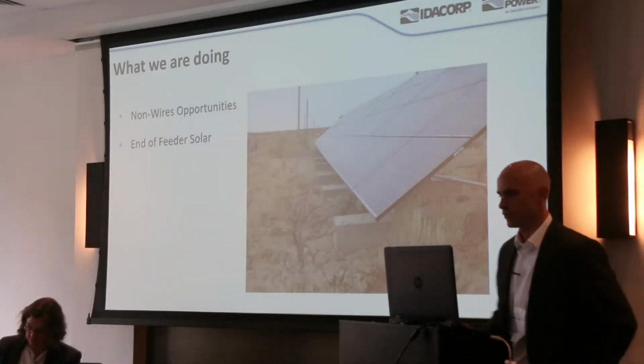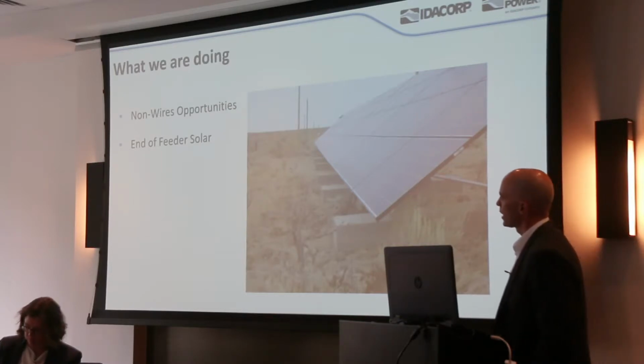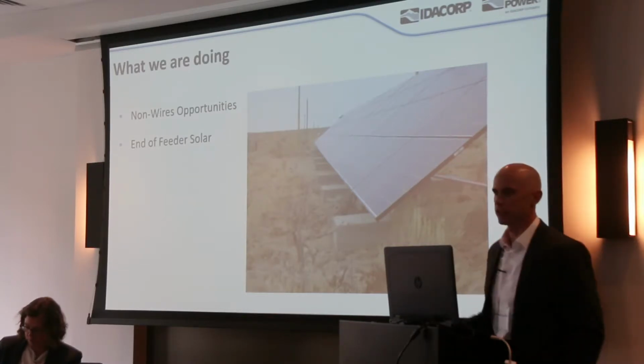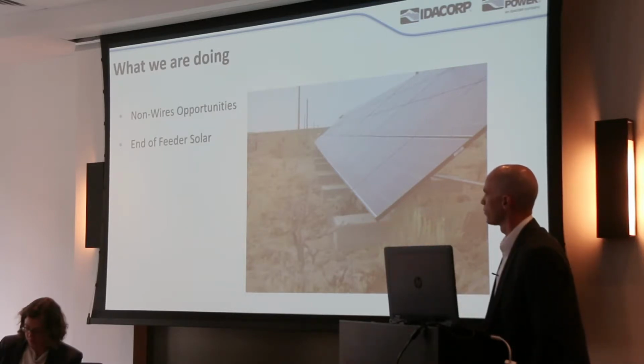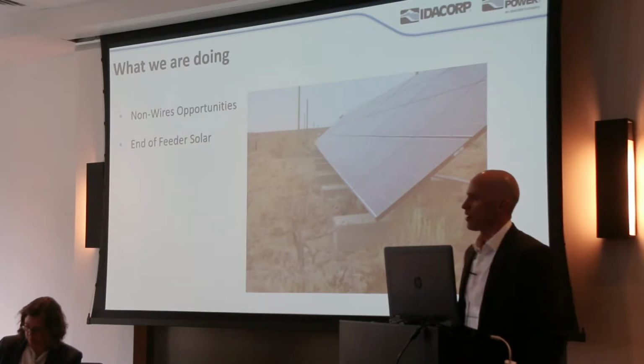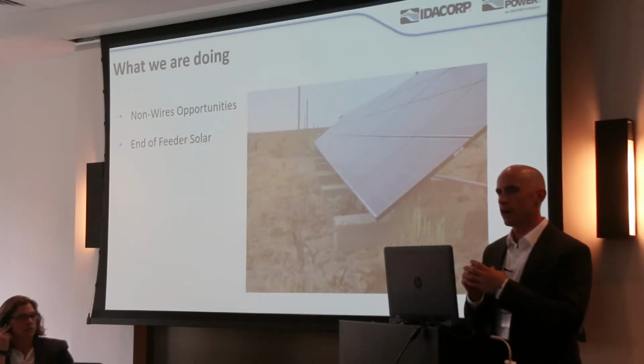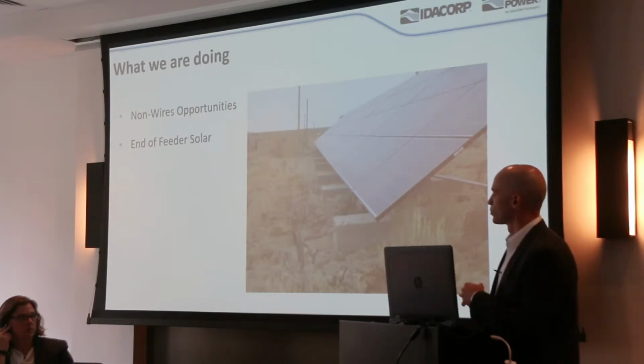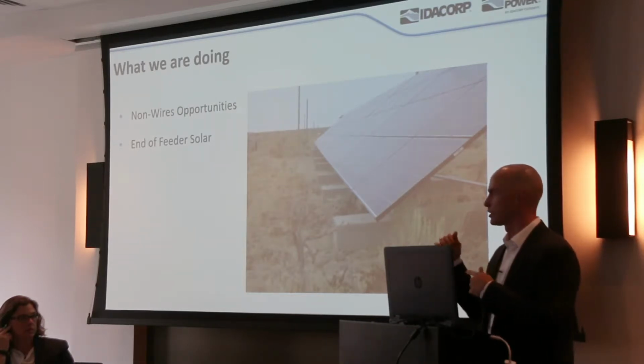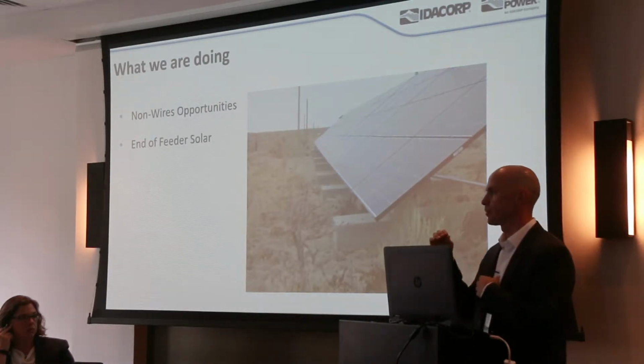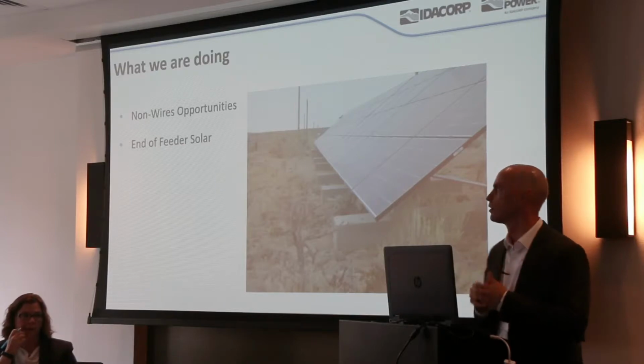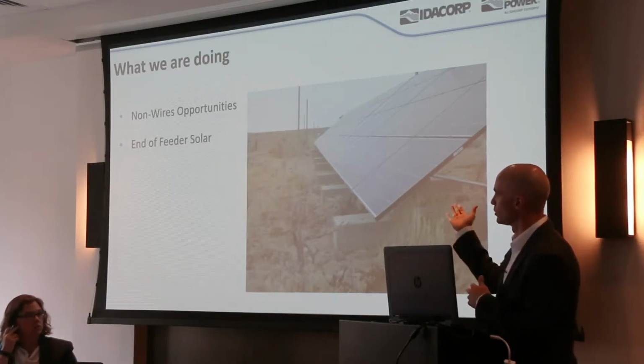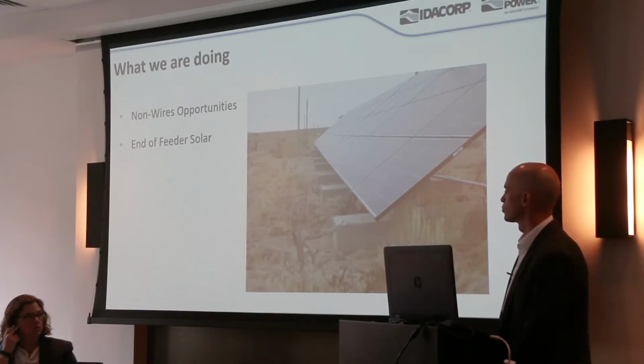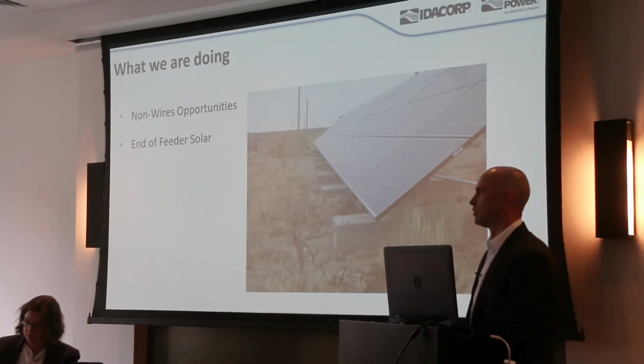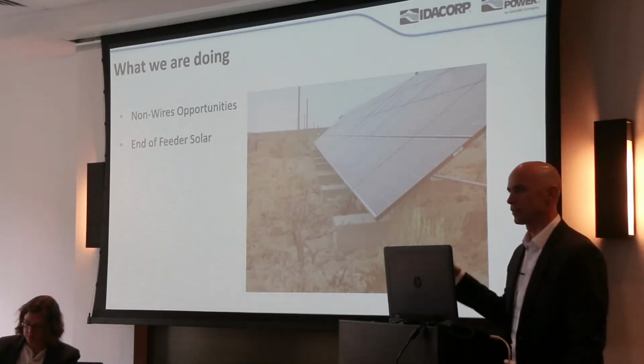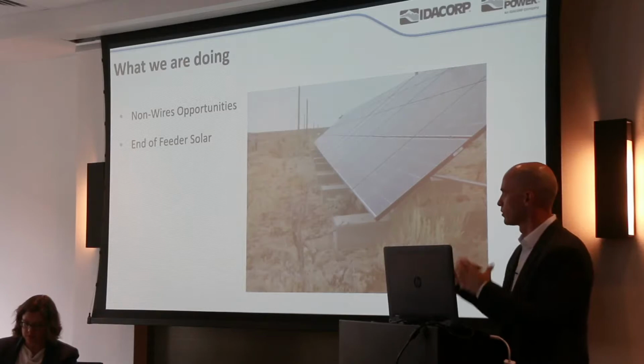One example is a solar array at the end of a feeder—a distribution line—in a remote area south of Fairfield, Idaho. We found a unique application where, instead of upgrading wires, we put in a solar array, and the output was timed with the period when we had the reliability issue: a peak load causing voltage problems. So instead of new wires, we used a solar facility. That's just one example; we have processes in place to look at these as alternatives to traditional upgrades for all projects.